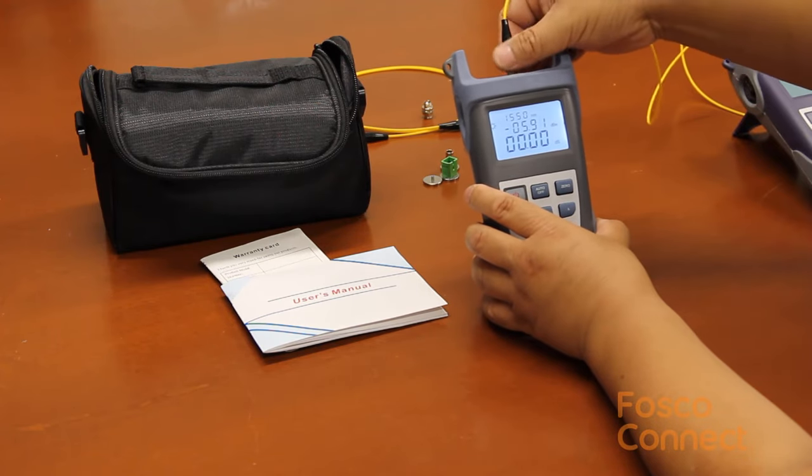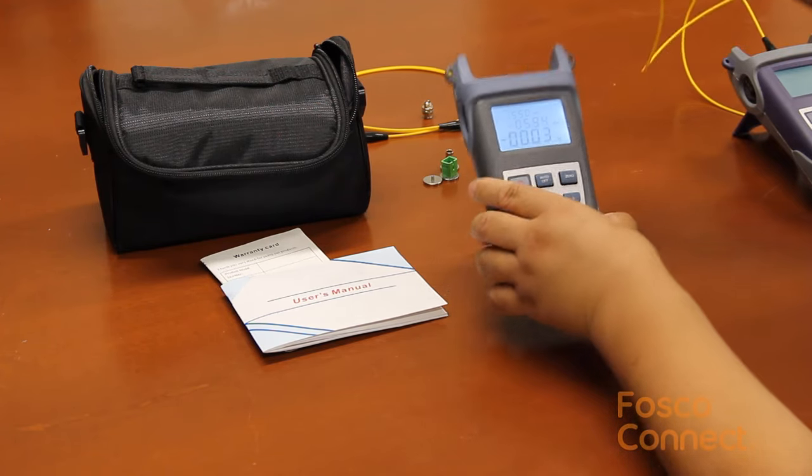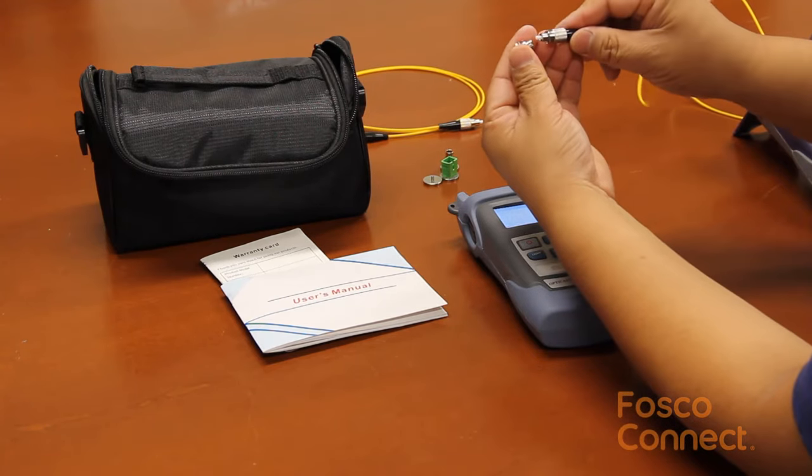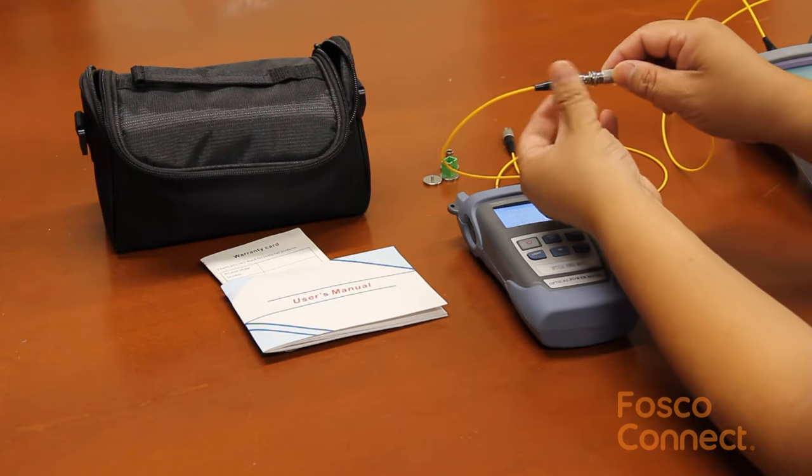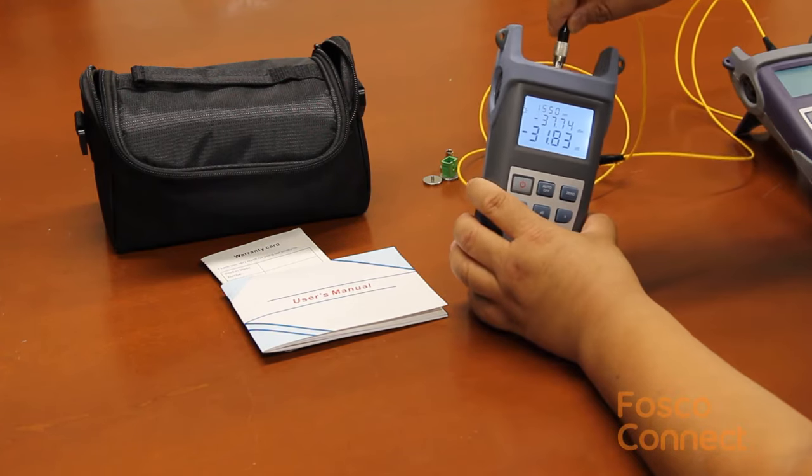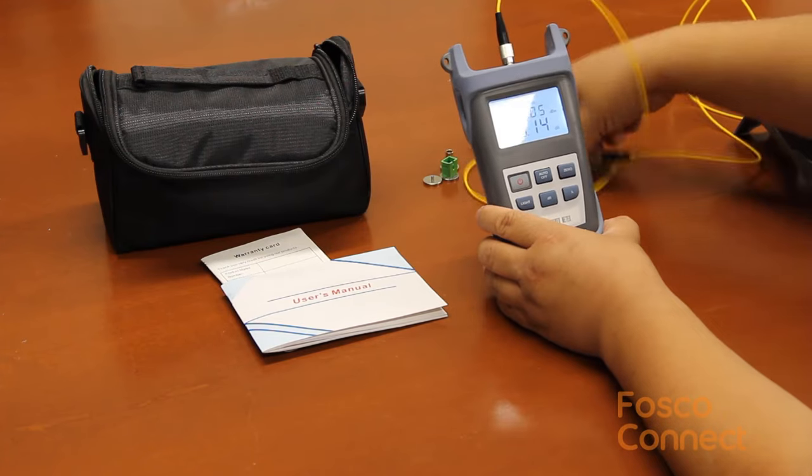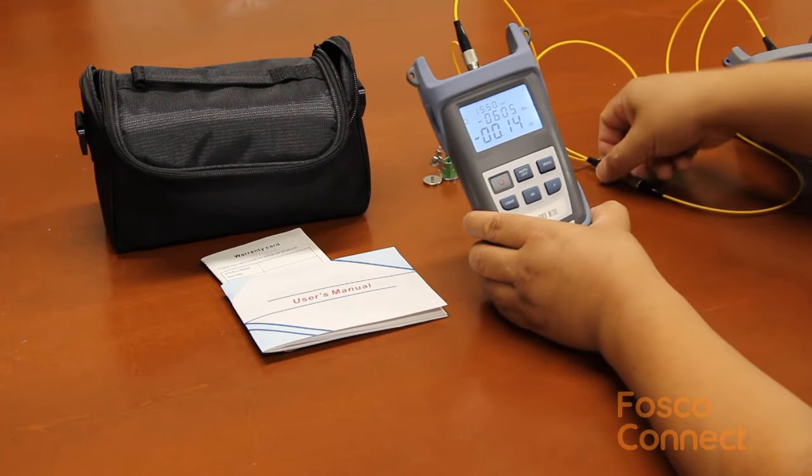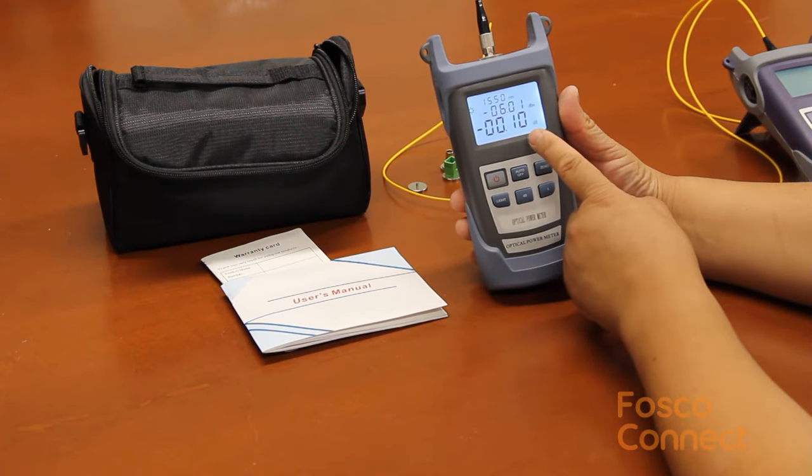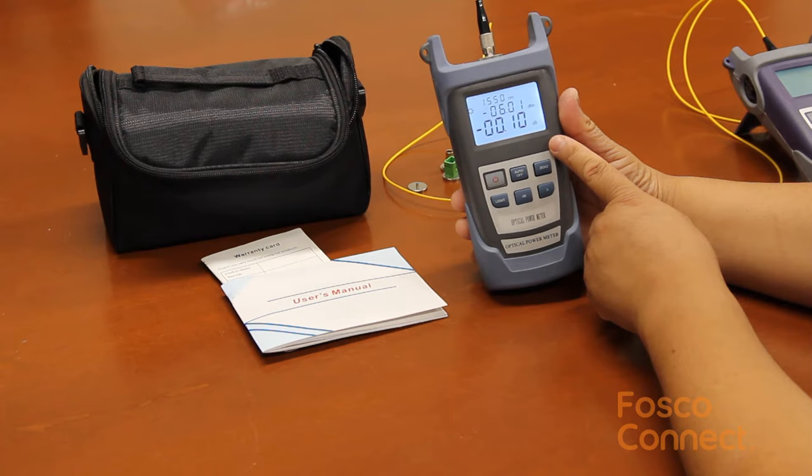Now let's plug in our jumper cable under test. Plug in one side to the light source adapter and the other end to the power meter. Let's make sure the cable is not under any stress. Now the power meter reads as negative 0.1 dB insertion loss.